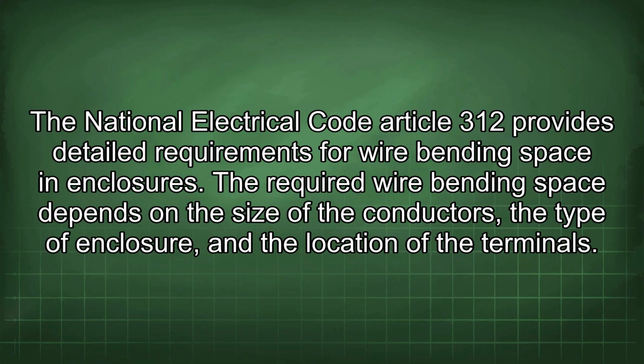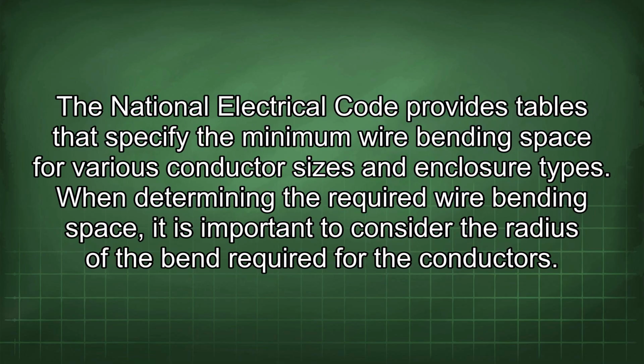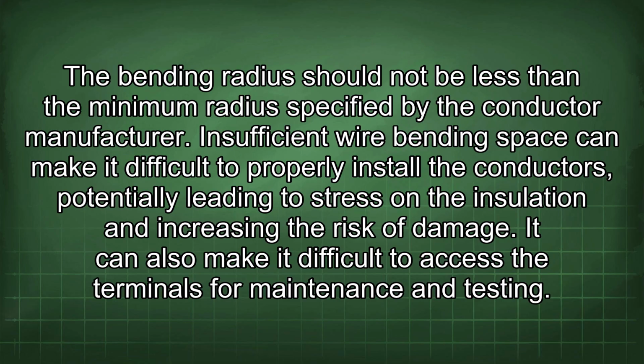The National Electrical Code Article 312 provides detailed requirements for wire bending space in enclosures. The required wire bending space depends on the size of the conductors, the type of enclosure, and the location of the terminals. The National Electrical Code provides tables that specify the minimum wire bending space for various conductor sizes and enclosure types. When determining the required wire bending space, it is important to consider the radius of the bend required for the conductors. The bending radius should not be less than the minimum radius specified by the conductor manufacturer.